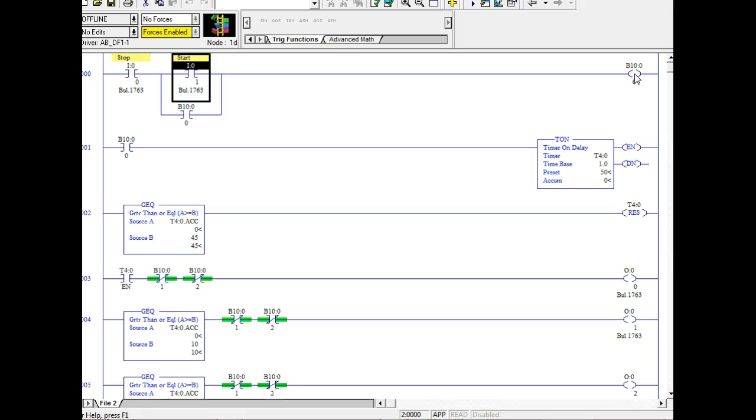So on motor controls, you could have true loads, not coils. You could have true loads inside the logic, but they've got to be low current loads. Your high power loads that require real high voltage, those are going to be outside in your power circuit, right? Y'all understand that? So that means that I've only got so many outputs to work with.